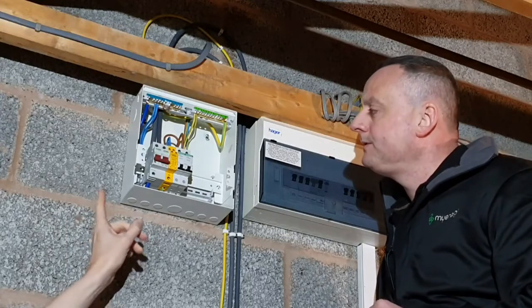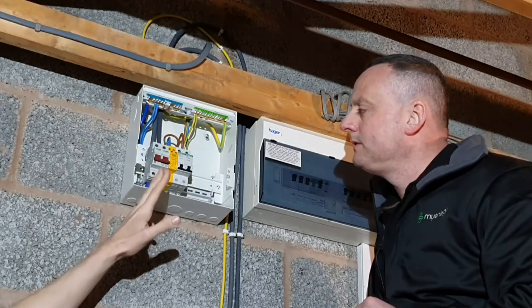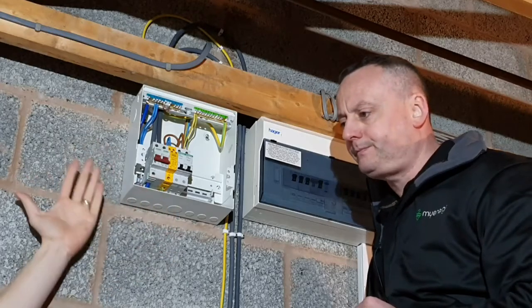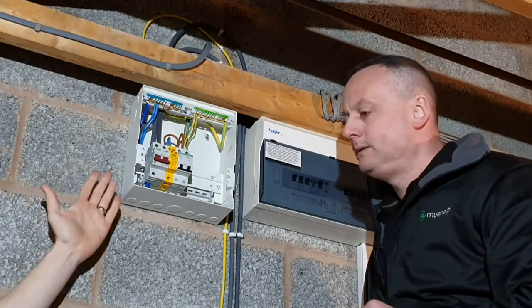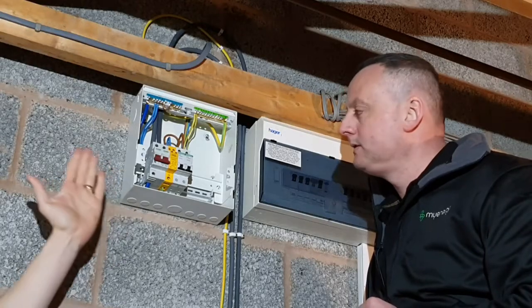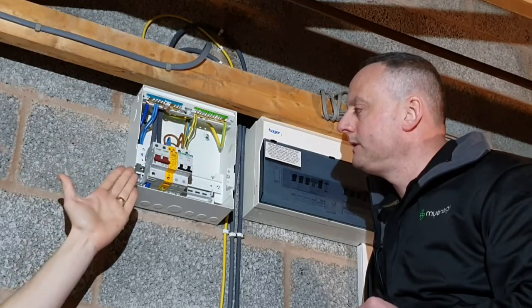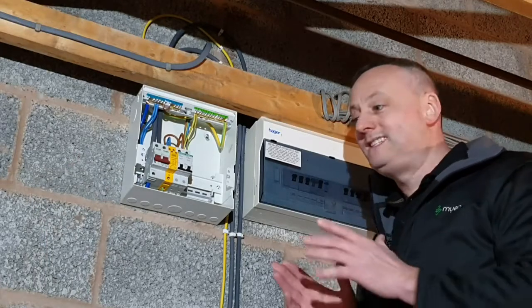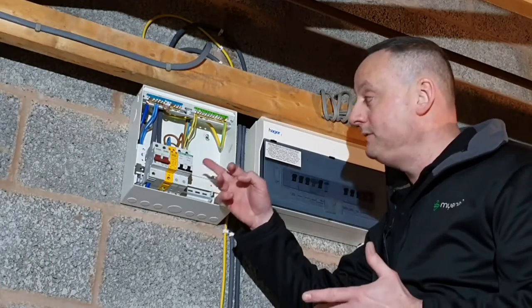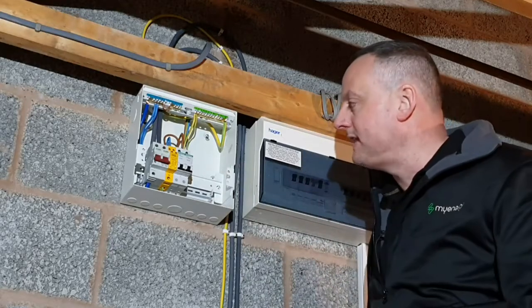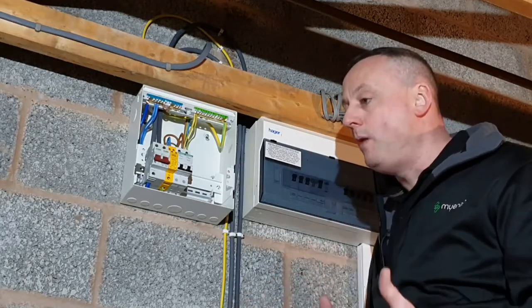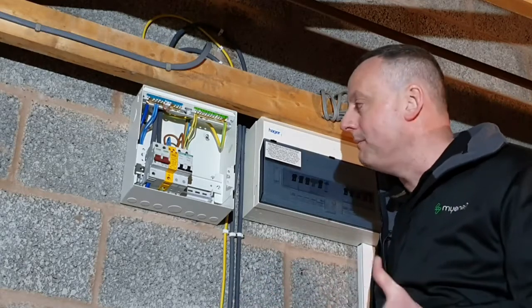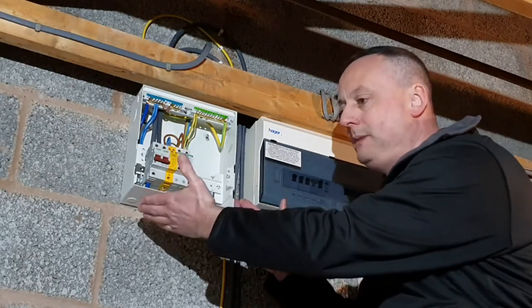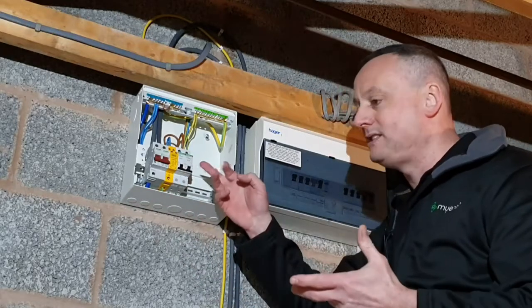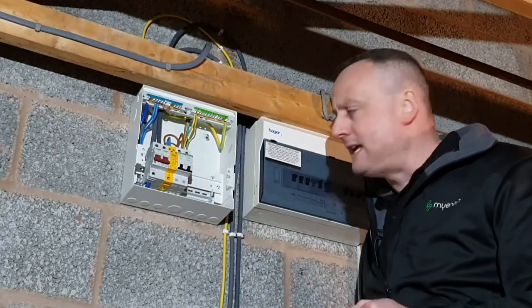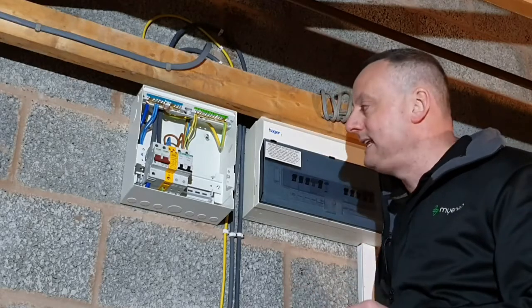If, however, we decided that we were going to protect our cable feeding the EV charging unit, maybe the cable's buried in the wall or something like that, and it doesn't have earth protective conductors around it, armouring and such, then what would we need to think about with the RCD protection for that cable, Gary? Yeah, it comes now down to selectivity. If there was an earth fault and an RCD was installed here, we know there's RCD technology also in the Zappi 2, which one of those RCDs is going to operate, and therefore the selectivity issue comes up. For me personally, with no other circuits being in this consumer unit, I wouldn't be bothered if the RCD in here tripped or the one in the actual Zappi 2 was to operate, but you've got to consider selectivity.